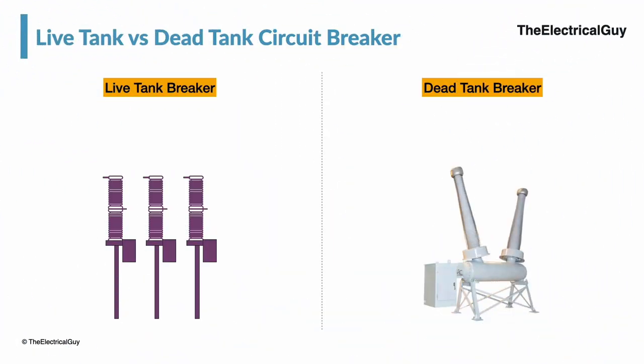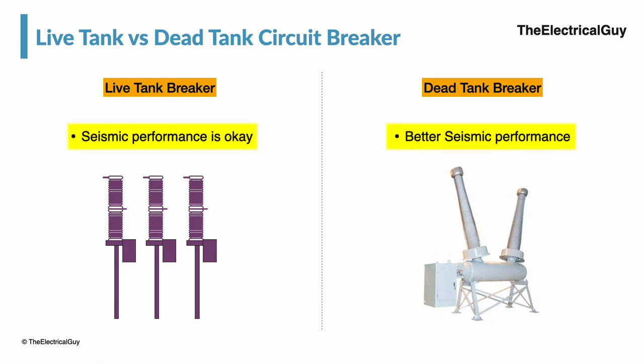Dead tank circuit breakers have fewer joints than live tank circuit breakers, as can be seen by looking at the images. As a result, dead tank circuit breakers offer better performance in areas where earthquakes are frequent — in technical terms, better seismic performance. Live tank breakers also perform well under different seismic accelerations, but compared to dead tank circuit breakers, the dead tank design scores higher in seismic performance.